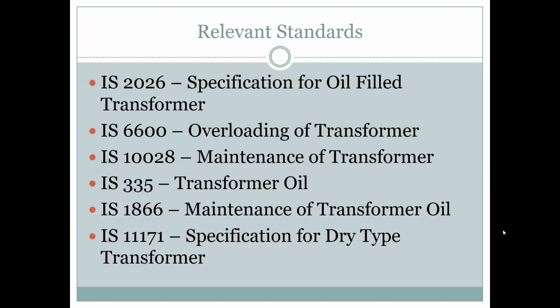It says that every overloading, if you overload the transformer by say 20% or 30%, the life of the insulation comes down drastically. Insulation failure takes place. So to get the mean average, if you run the transformer at 10% overloading, there is also a limit, 10 to 20% overloading. You have to underload the transformer during the 24 hours of operation to regain the life of the insulation. By plotting how much overloading you are doing and how much underloading you are doing, you get a K factor. That is the governing factor of how much overloading we can go. But as per the transformer IS, overloading is not allowed. That's why when transformers are rated and designed, people load up to 80%, 75%, like that.